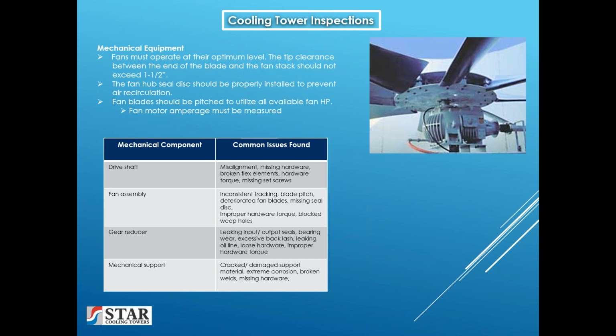The fan blade should be pitched to utilize all the available fan horsepower. So the plant electrician should measure the fan motor amperage to compare that to the nameplate amperage of the motor. You don't want to use every bit of the nameplate because of the changes in air density, but you want it to be slightly below the nameplate amperage.